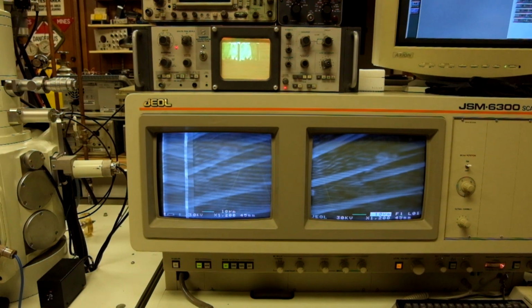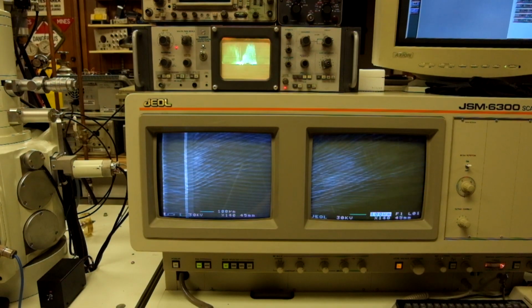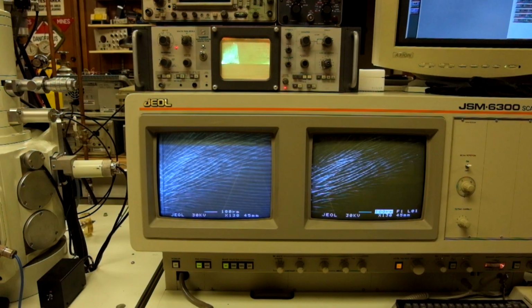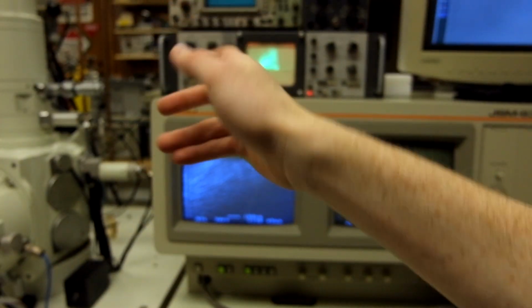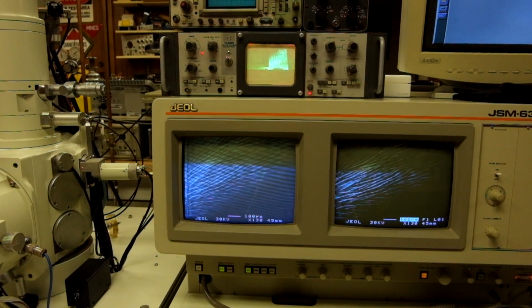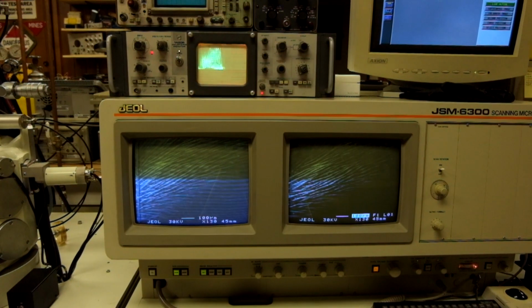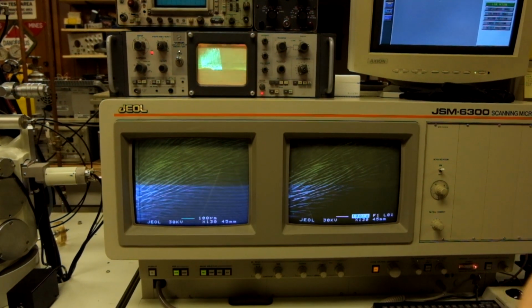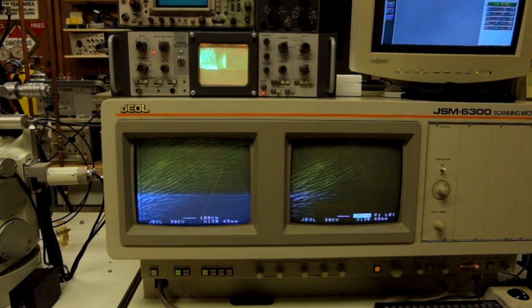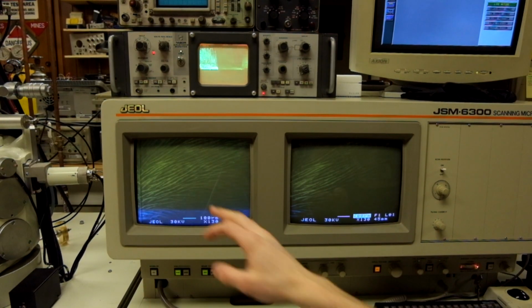Now, if I wanted to actually grab really high-resolution images, there's a few things I would do. The first thing I would do is put the filament at its absolute saturation, so at the second peak. I would go over to the aperture right there, and I would close that in. Right now we're at aperture setting 3, which is a pretty wide aperture. So I would close that in, and that would physically give us a smaller electron beam. Then I would lower the probe current, which further gives you a smaller beam. I would make sure the acceleration voltage is maxed out at 30 kV. Then I would redo a gun alignment for tilt and shift, and I would also center the aperture by engaging the wobbler here, and it's actually pretty well centered right now.